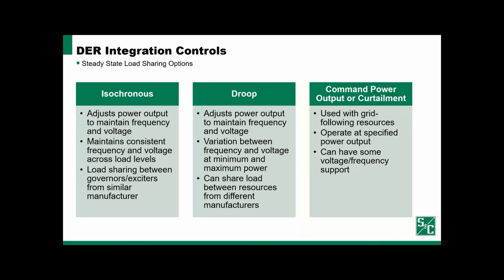Now, this can be particularly impactful in microgrid or islanded systems where we have a very limited amount of generating resources. And small changes in load, not as small as a light switch, but more significant changes in load, can have an impact on the system dynamics. We need to think carefully about when load turns on, what resource is going to adjust its output to accommodate this changing load. And there are two major ways that we do this. One is with isochronous.